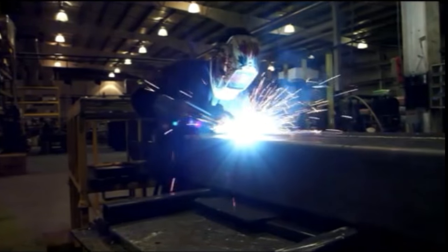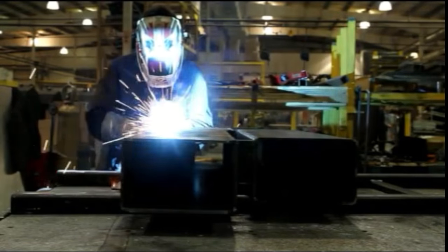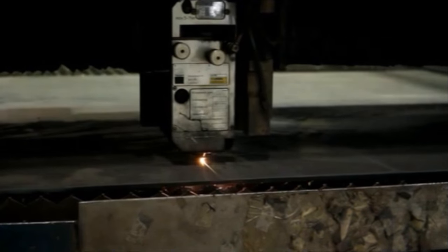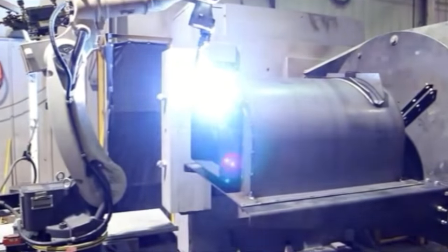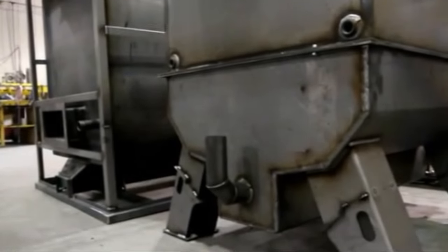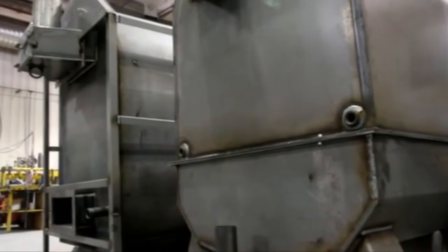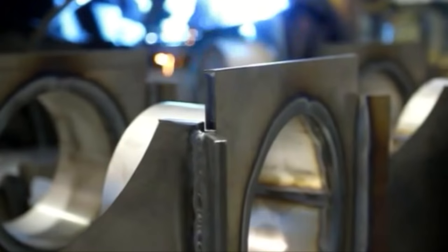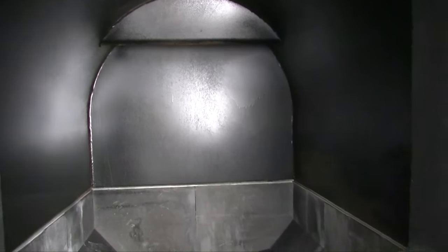The Ultimizer achieves both, therefore burning a third to half less wood fuel than other industry boilers. Double welded boiler style joints are exclusive to Portage & Main outdoor water furnaces. All parts are laser cut for precision fitting, which allows the bevel to be double welded for total penetration welds. Welding inside and outside takes more time but it's worth it, as it helps prevent weld corrosion, cracking, and pinholes. Fire chamber and heat exchanger are made of quarter inch W44 cold roll steel, which eliminates problems associated with other metals. Rounded fire chamber top requires fewer welds. Inside water jacket is made of quarter inch cold roll steel, and outside of the water jacket is made of three-sixteenths cold roll steel.